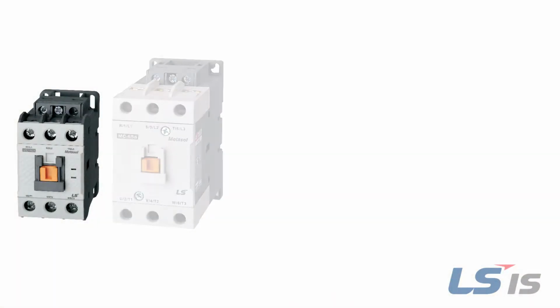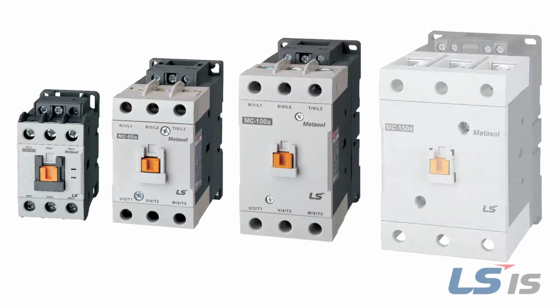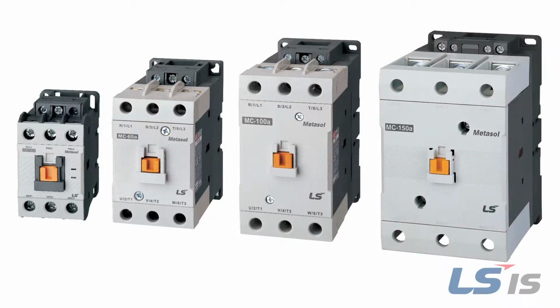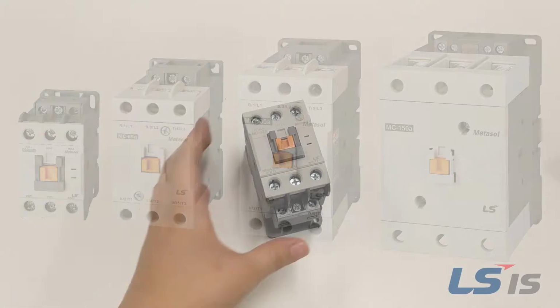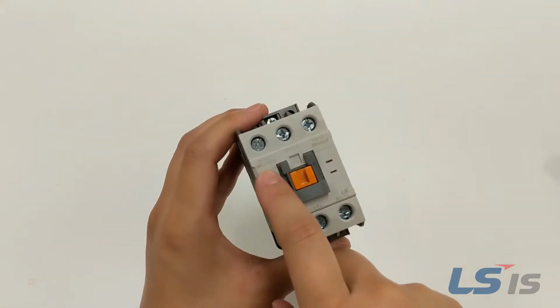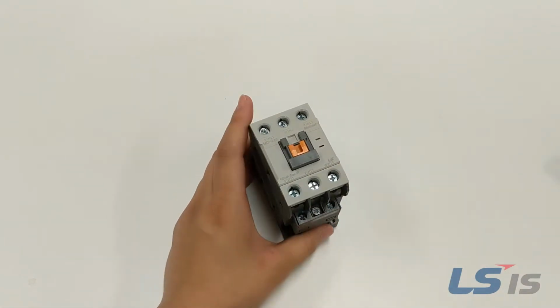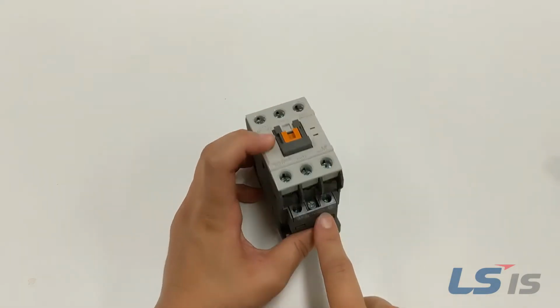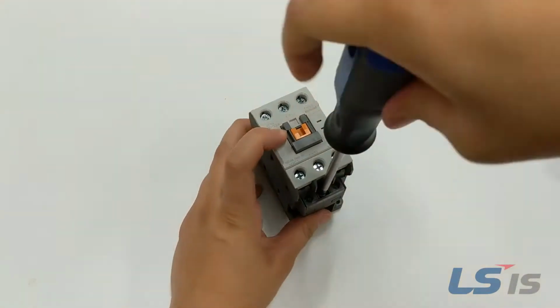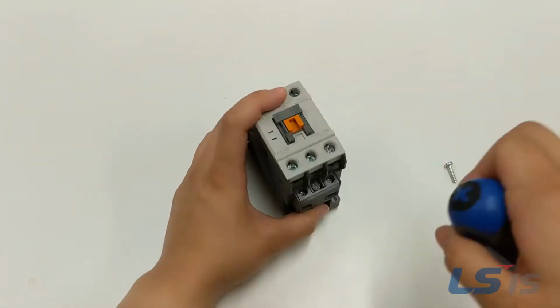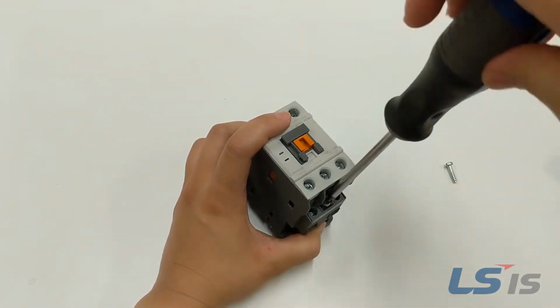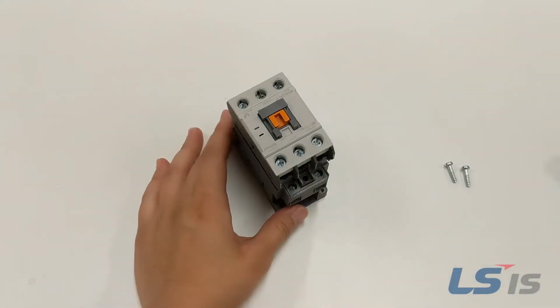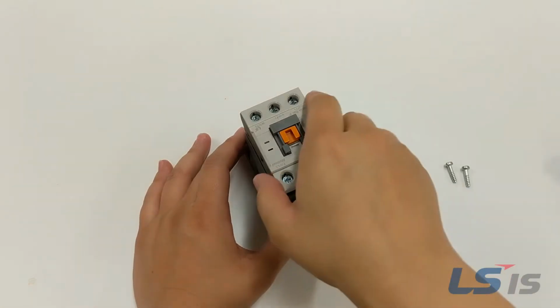For the MC 40M frame to 150M frame contactors, remove the contactor from the box and set on a flat surface. Remove any auxiliary contact units and cut any nameplate labels along the seam of the contactor. Next, remove the center screw between A1 and A2 on each side. Note that the 150M frame has two screws on each side. Pull the top half off the bottom half and take out the spring.